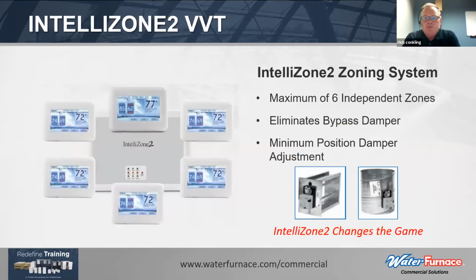The IntelliZone 2 zoning system has the capability of handling up to 6 independent zones of control. Because of the virtue of its variable speed, direct drive ECM blower motors, we eliminate the need to introduce bypass dampers to reduce airflow coming back from the space when zone dampers are closing off. The zone dampers themselves do have minimum adjustment positions to maintain minimum airflows in each of the zones at all times. And really, IntelliZone changes the game in terms of thinking about a water source heat pump.